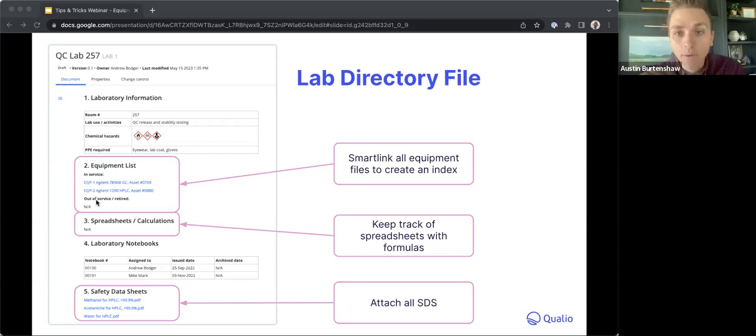Auditors typically ask how many pieces of equipment, how many of those require CAL, PM, both CAL and PM. That guides them on how many records to sample. They often ask how many were calibrated in the past 12 months and how many were found out of tolerance. And then he says in parentheses, this is needed. So not necessarily a question in here, but what have you seen, Andrew, within your process when you're going through an auditing process within equipment management, but also how do we utilize Qualio for equipment management from the auditor side, from Chance's remarks?